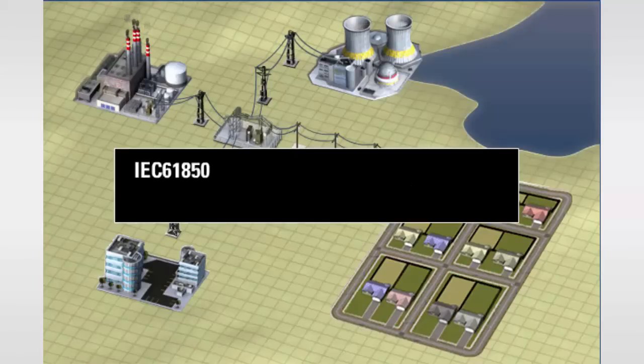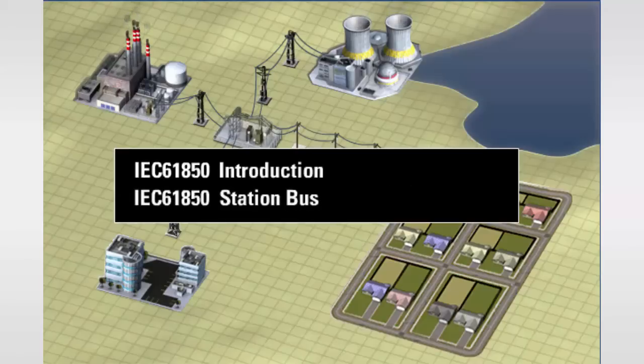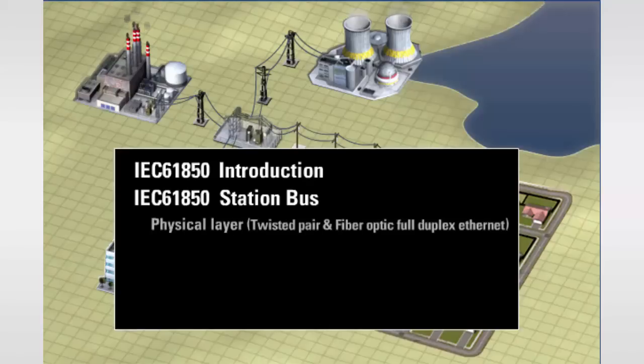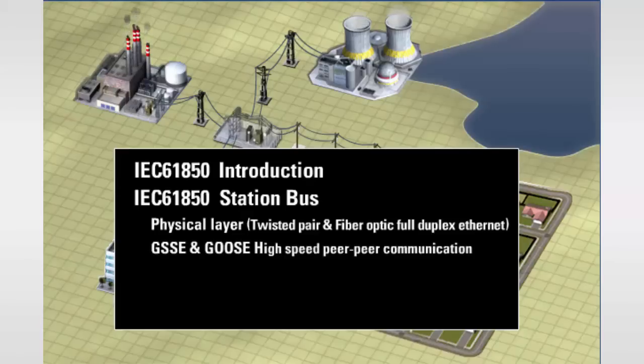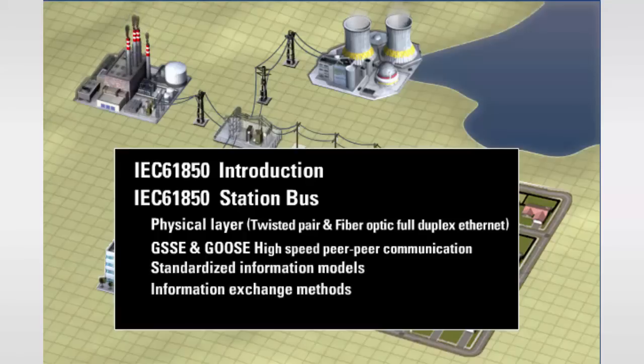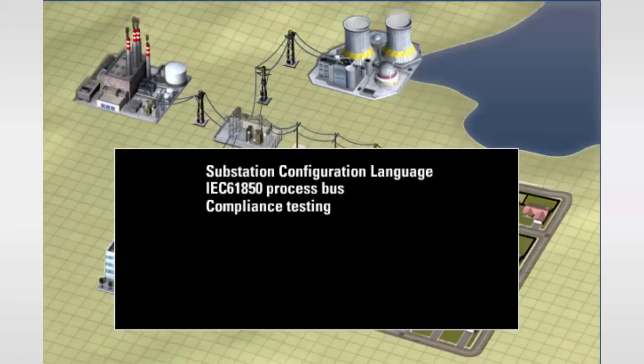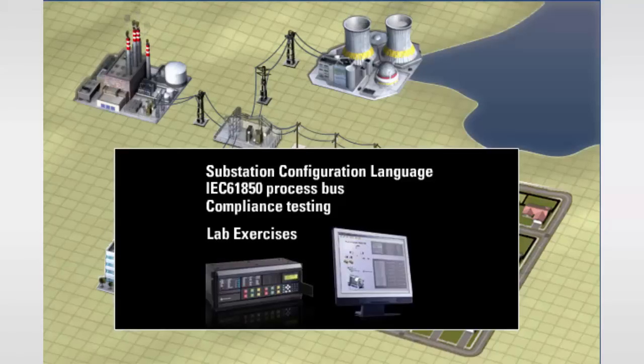After a brief introduction to the IEC 61850 protocol standard, we'll focus our attention on the IEC 61850 station bus portion of the protocol. This will include the station bus's physical layer, both twisted pair and fiber optic full duplex Ethernet, the GSSE and GOOSE high-speed peer-to-peer communication services, the standardized information models, the information exchange methods, and the client server services. The course will also touch on the substation configuration language, the IEC 61850 process bus, and compliance testing. These sections will include lab exercises to assist in better understanding GE Multilin Universal Relay and EnerVista Viewpoint Monitoring's implementation of the IEC 61850 protocol.